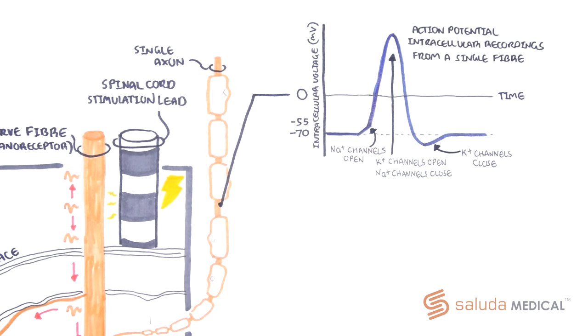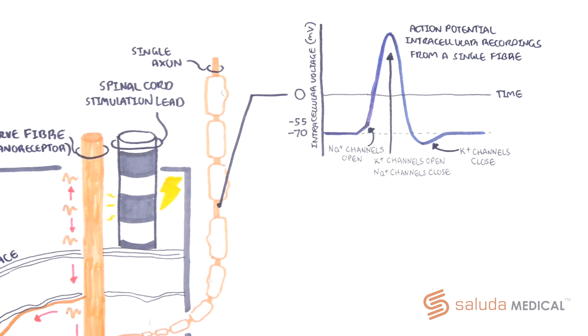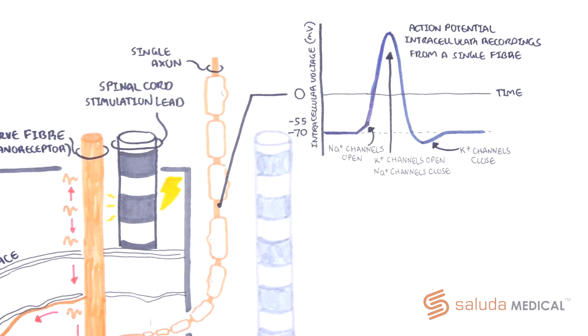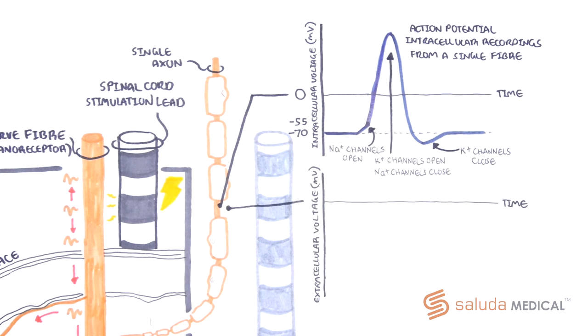The evoke spinal cord stimulation system can detect voltage changes in the spinal cord from an epidurally placed lead, which means it is detecting extracellular potentials from outside the cell. As such, the shape of the signal recorded will look like a mirror image of that measured intracellularly.